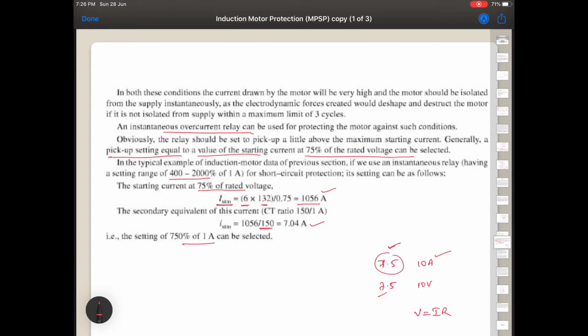Okay, and if the relay senses a current beyond 7.5 ampere, then it will give a signal to the circuit breaker. So the relay now acts as an instantaneous current relay, or instantaneous overcurrent relay, and once it senses 7.5 ampere, it gives a tripping signal to the circuit breaker. Hence a short circuit current as high as 7.5 in the secondary is being tripped.